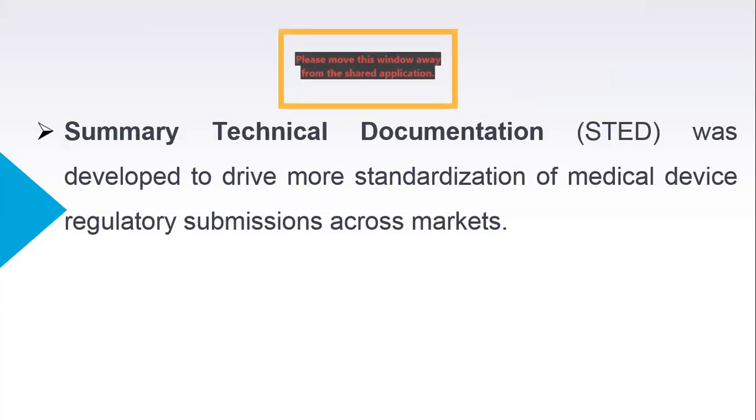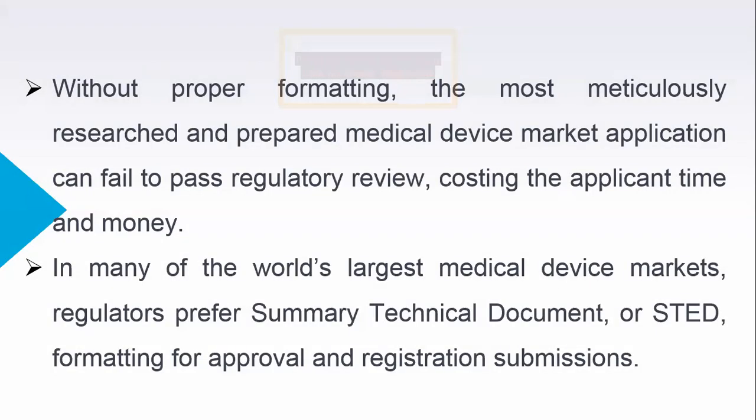So to avoid that, the GHTF, which has now been replaced by the IMDRF, introduced one technical document that is called summary technical documentation. So every manufacturer has to follow this STED format to submit their technical information to get approval before the device can be released into the market, right? Without proper formatting, the most meticulously researched and prepared medical device market application can fail to pass regulatory review.